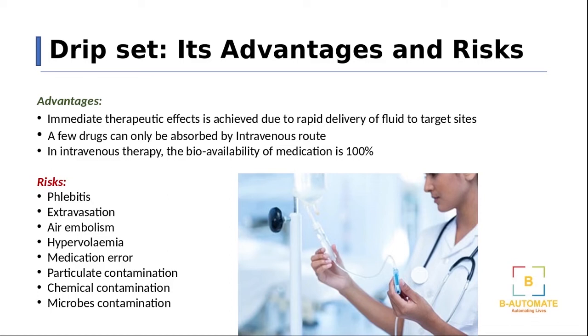Drip set consists of a fluid reservoir and a capillary tube of fixed diameter for fluid to pass through, called a drip chamber, and the drops formed will drip from the tube into the chamber when they reach a certain volume. To produce a fixed number of drops per unit time, the clinician adjusts the flow rate.